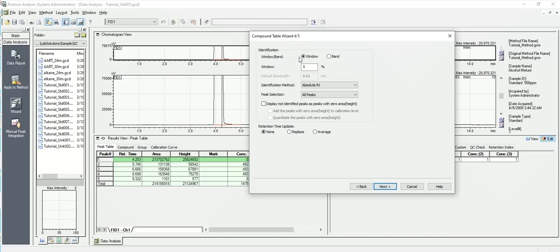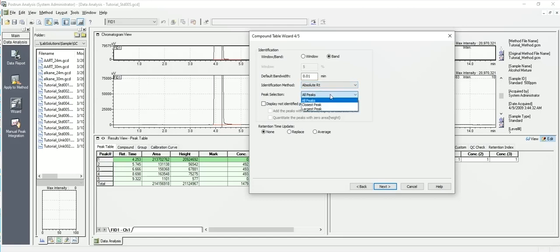So here we have window or band. In GC we always use band because there's going to be so many peaks that the window would open up too far. We'll stick with the default bandwidth right now. You're going to want to use absolute retention time, and we're going to want all peaks, okay, no updating a retention time for now.